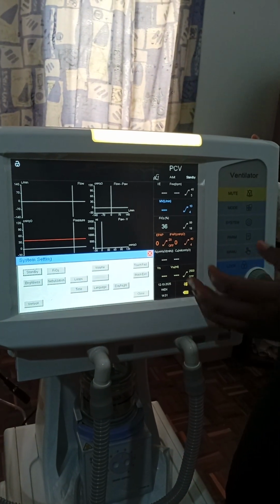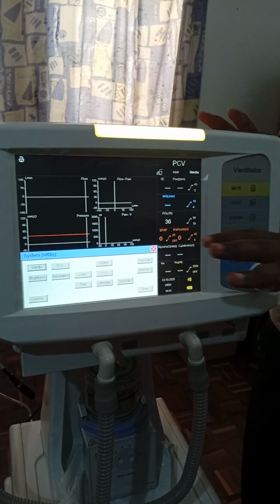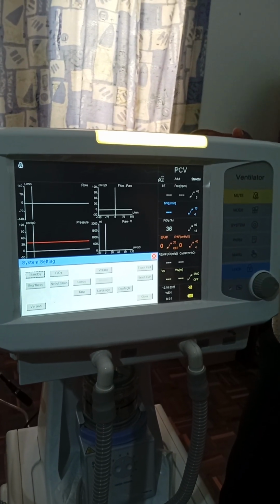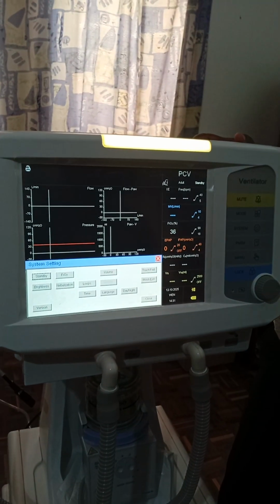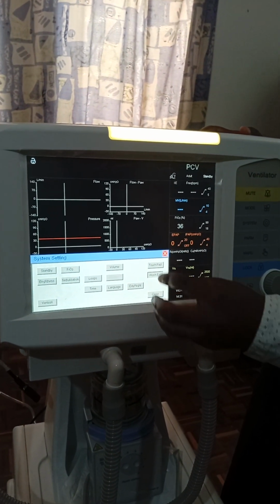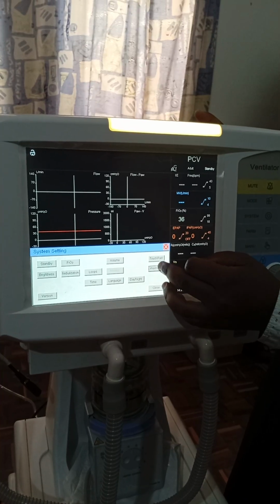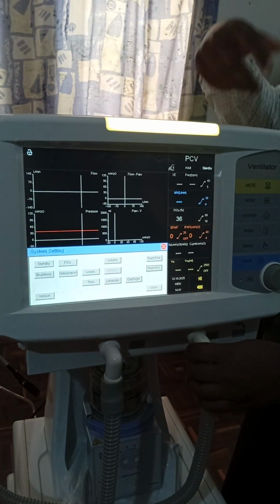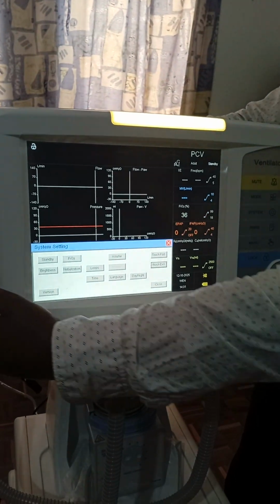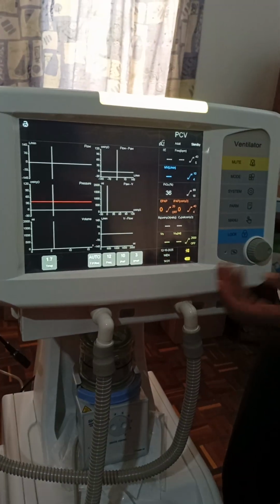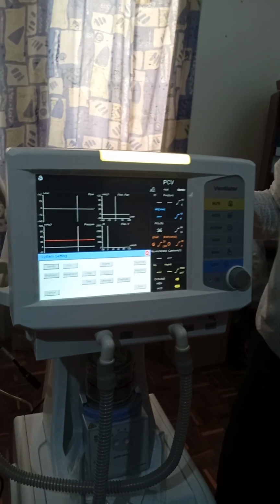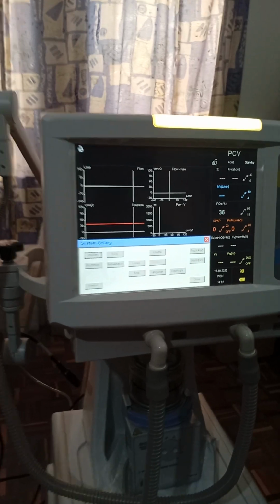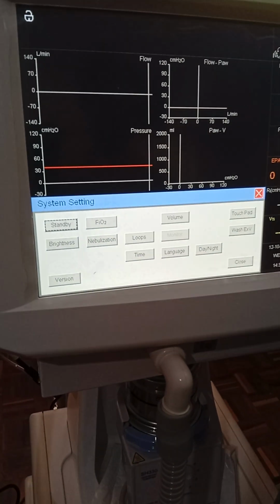Here again, after every patient, once you've done all the cleaning and you've connected the tubings, you need to clean the machine. You need to come and select wash. If you select wash and the machine is already connected to the gas and running, you'll feel some air coming out of the exhaust valve here. And then the machine will have already cleaned itself. For the language, you don't need to change, it's already in English. If you change, it will go to Chinese, and it will be a challenge for you to adjust the language.